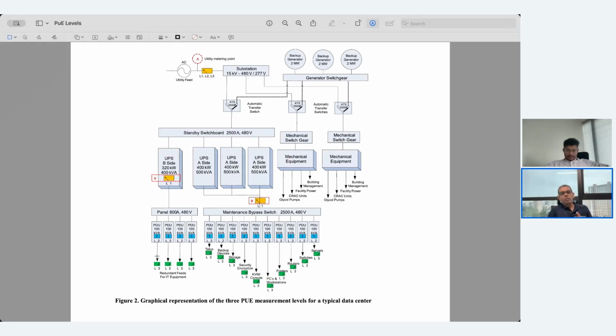And the more advanced, and I would say the preferred one if you really want to focus on PUE enhancement, is level 3, which primarily talks about all the IT equipment input energy sources. So you're talking about your racks, your storage devices, your workstations, your routers, switches, servers, all of these directly at the point of measurement. So you're going directly to the point of measurement at these places, all your metered rack PDUs and so on. That's level 3.